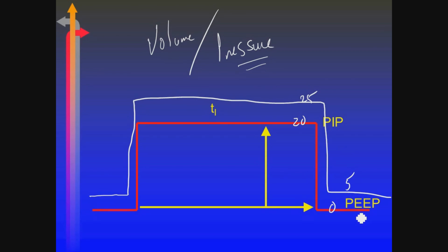They move together. When I say that I'm delivering at a certain pressure, it's always above the baseline. So if I raise the floor, it's got to go up higher. That's a great question, Liz. You don't know why yet, but when we talk about non-invasive ventilation, it's a different story. Or in some neonatal ventilators, a different story.